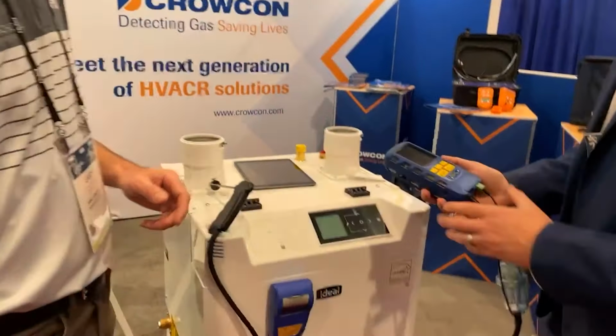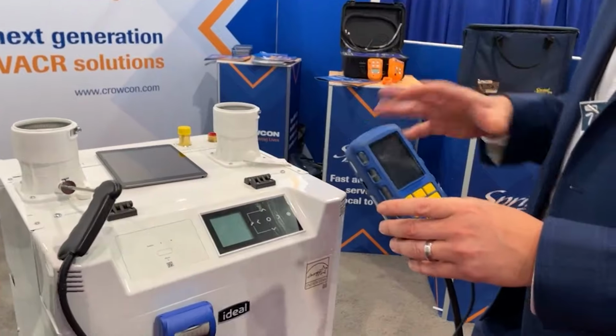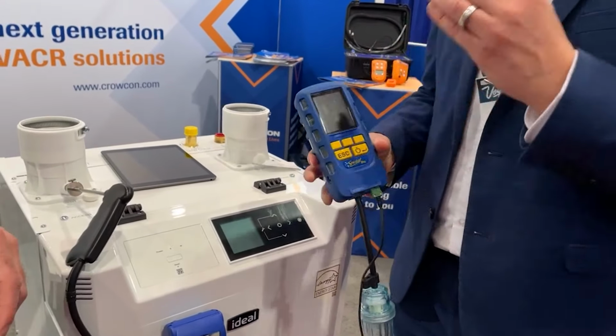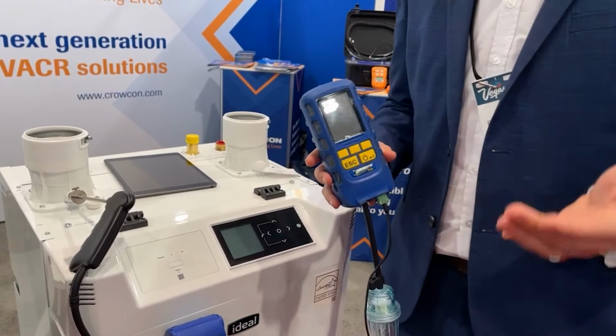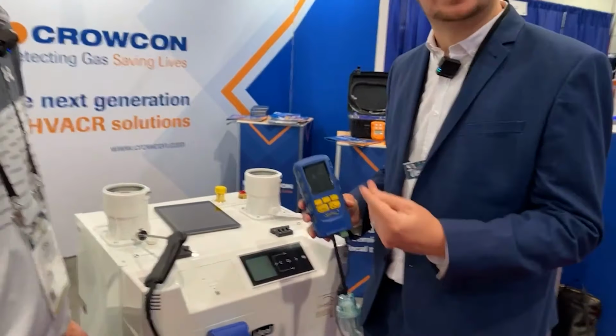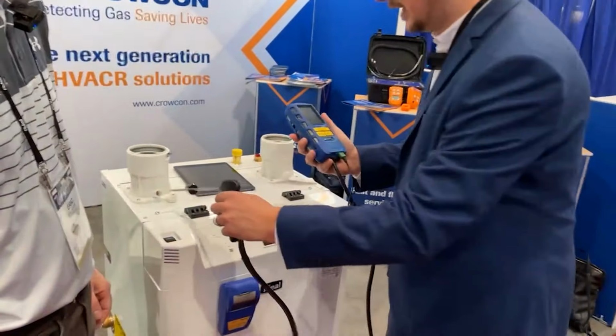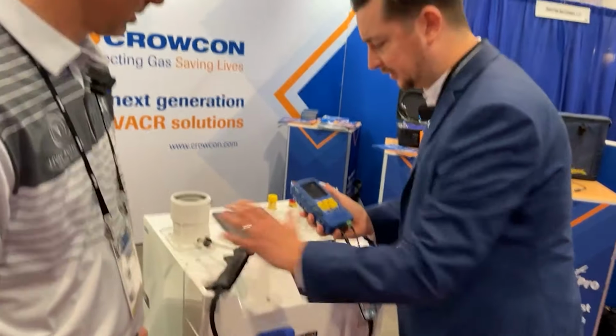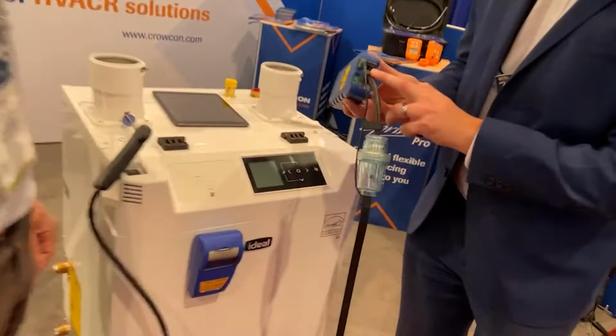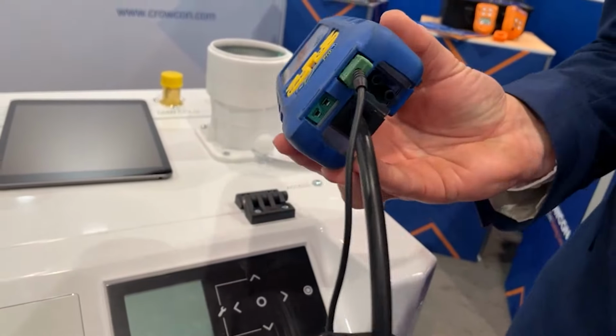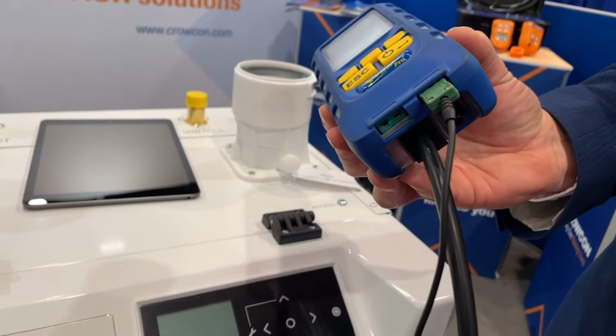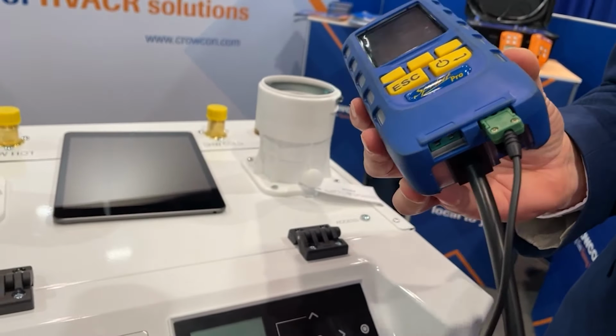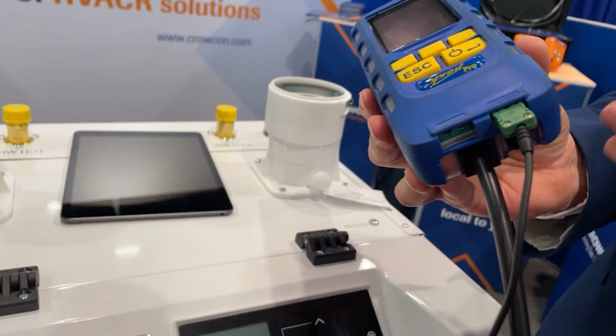Okay, so we've got some good stuff in here. First of all, there's a few key values. The first one is it's not just a combustion analyzer, it's a true multi-tool experience for the contractor, so they're getting efficiency and value - many tools in one. Yes, it's a combustion analyzer, we've got the probe here, we put it in the flue and it does your combustion analysis. But it's also a manometer - you've got your pressure terminals on the bottom here, and you can do let-by testing, draft pressure testing, differential pressure testing. There's a full suite of pressure testing functionality in there.